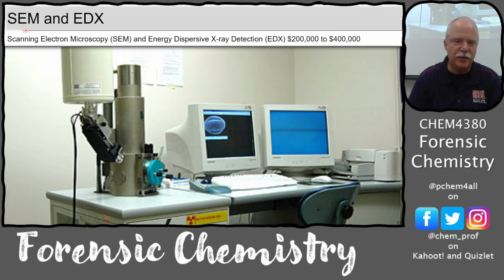Okay, so this is the sample chamber right here. The samples go in this area. These little micrometer adjustments can adjust the tilt of the sample and move it around left and right so that you can get the image all in there. It's kind of like a microscope. You move the stage left and right. These controls are all up front. A lot of these will also have motorized stages inside, so you can do that on the computer too. So these are probably gross adjustments, and then inside the computer you can move it around. Up here is the electron source, which we'll see in a second, sort of the breakdown of this thing.